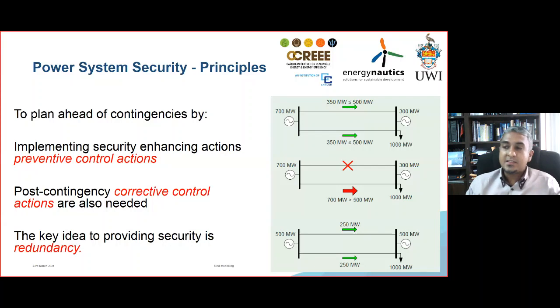What I have here is a diagram that illustrates this. It suggests that if we have a power system with a load of 1000 megawatts and generation of 1000 megawatts, supplied by 2 lines, you would ideally want these lines utilized and pushing as much power through as possible. However, these lines have a rating, and in this case they're rated at 500 megawatts. So the most economical way of generating power is not going to be the most economical way of transmitting the power. What you have to recognize is that if there's an outage and you lose one of those lines, you'll potentially have a violation, which leads to the cascading story you heard before.